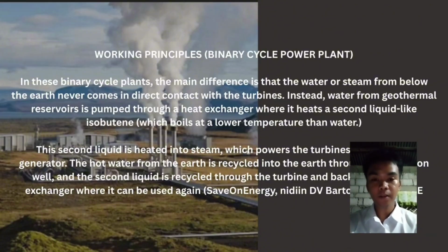In this type of power plant, the geothermal water extracted from the underground reservoir does not directly contact the turbine. Instead, the hot geothermal fluid is pumped from the production well and passed through a heat exchanger. Inside the heat exchanger, the geothermal water transfers its heat to a secondary working fluid, commonly isobutane or isopentane. These fluids have a lower boiling point than water, allowing them to vaporize at lower temperatures. Once vaporized, the secondary fluid turns into high pressure vapor.